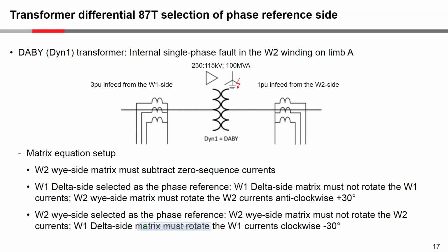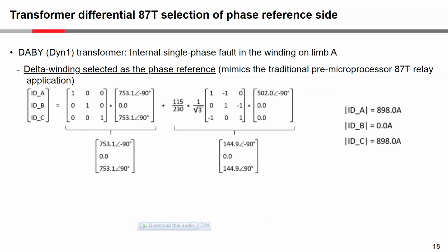So if the delta side is selected as the phase reference, then remember the Y side currents, the winding 2 side currents, must rotate anti-clockwise plus 30 degrees. So they have to go anti-clockwise. And if you choose the Y side as the phase reference, then of course the delta side currents need to get a 30-degree shift in the opposite direction. They need to go clockwise, because now the delta side needs to line up with the Y side. All right, so here I entered the values.